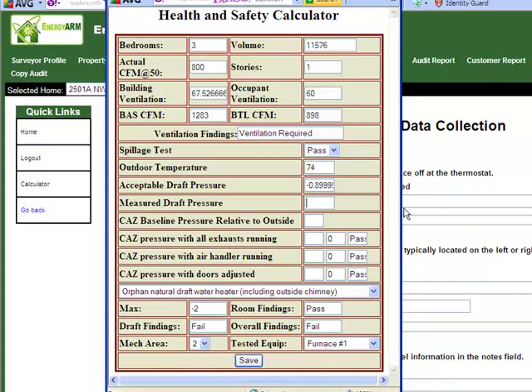If our measured draft pressure is not high enough — let's say negative 0.5 pascals — you'll notice that our draft findings at the bottom show failure. However, if we have a good draft pressure, let's say negative 2 pascals, our draft findings are now passing.